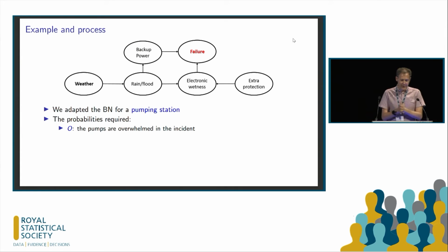first of all, this water pumping station also had a permanent flood barrier, which was 90 centimeters high. I'm taller than that. 90 centimeters high. And so it would fail if water got in over that flood barrier. However, if there was 90 centimeters of standing water outside this water pumping station, you've got all manner of bigger problems than it coming over the top. It'll have failed long before that.